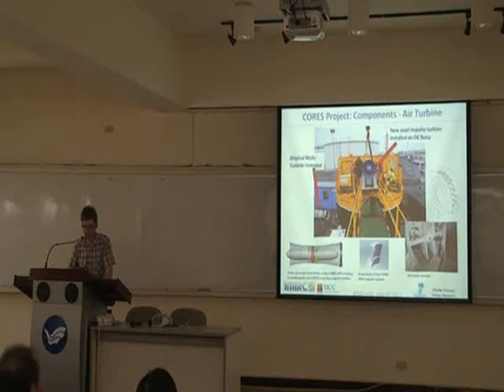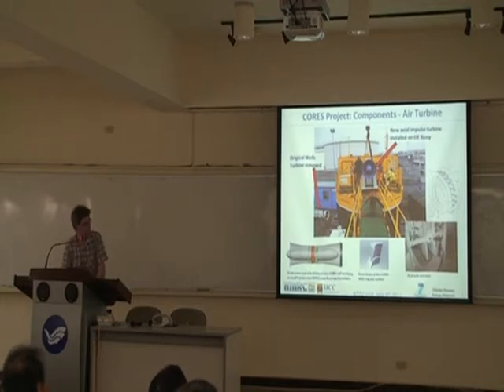So as part of this project, we changed a lot of the equipment. You can see the old Wells turbine down here was removed, and we put on this new turbine here, which is an impulse air turbine. Slightly less proven in terms of actual offshore testing or wave energy deployment than the Wells turbine. So that was one of the goals of this project, to look at this new component, and particularly with respect to the movable guide vanes.